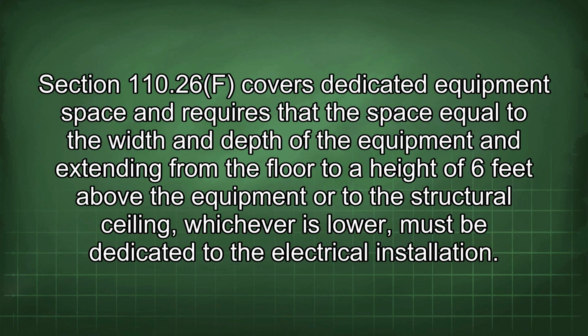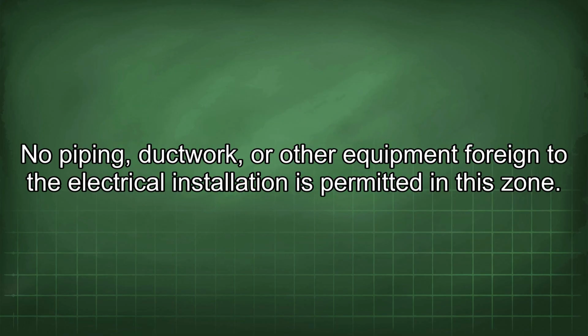Section 110.26(F) covers dedicated equipment space and requires that the space equal to the width and depth of the equipment and extending from the floor to a height of 6 feet above the equipment or to the structural ceiling, whichever is lower, must be dedicated to the electrical installation. No piping, ductwork, or other equipment foreign to the electrical installation is permitted in this zone.